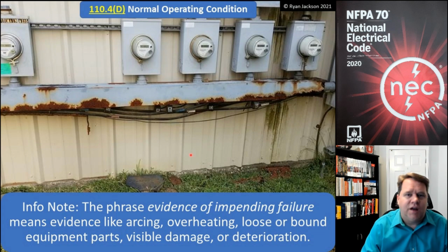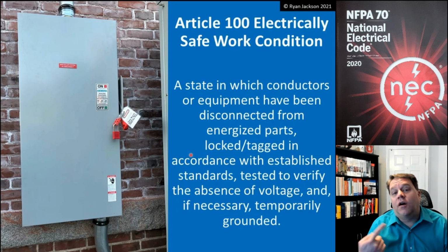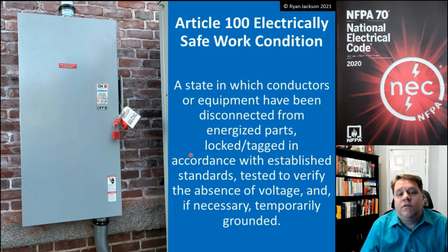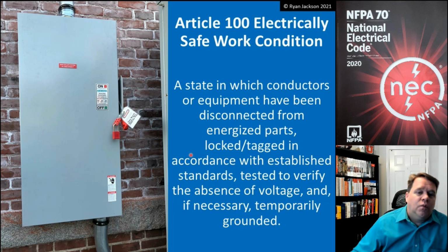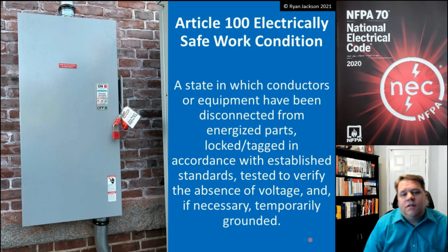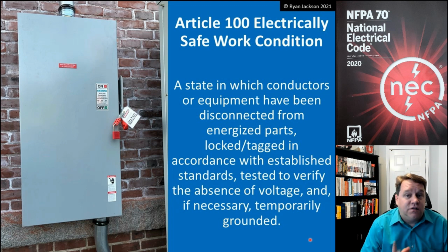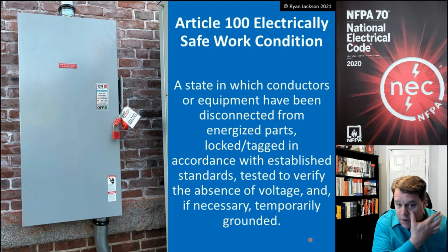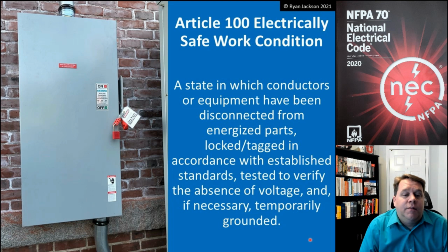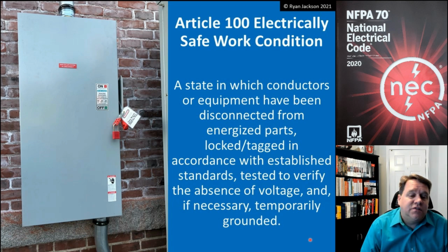Now, what is an electrically safe work condition? We've been talking an awful lot about it, but we haven't described what that means. Well, in Article 100, an electrically safe work condition is a state in which the conductors or equipment have been disconnected from energized parts, locked or tagged in accordance with established standards, tested to verify the absence of voltage, and if necessary, temporarily grounded. All right, so that's an electrically safe work condition.